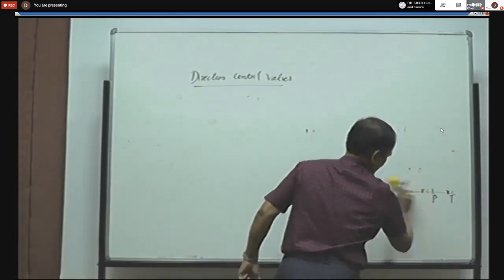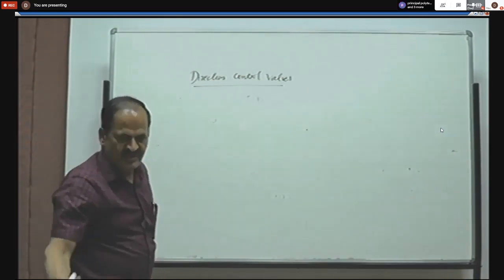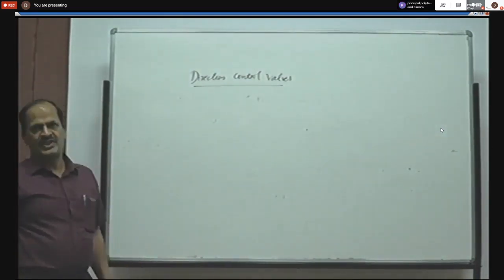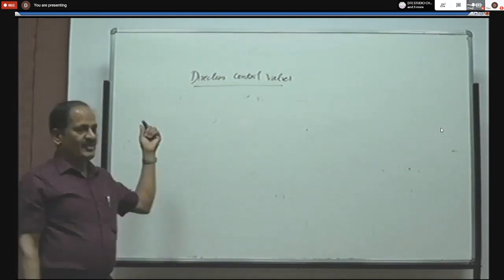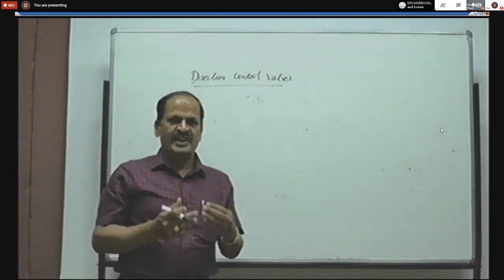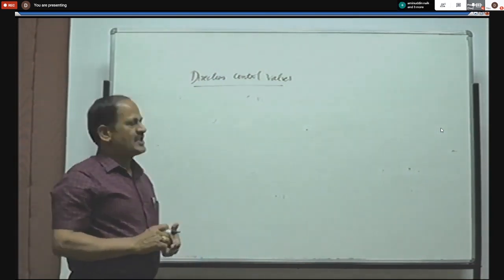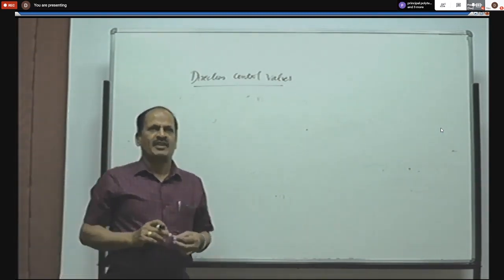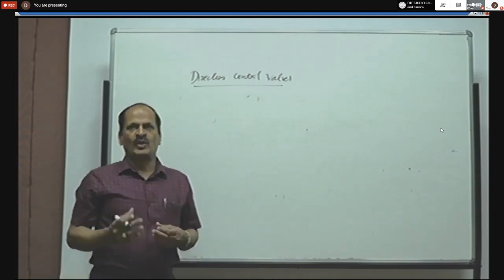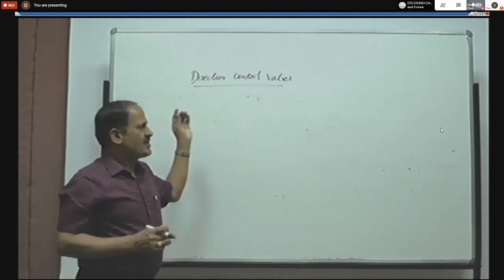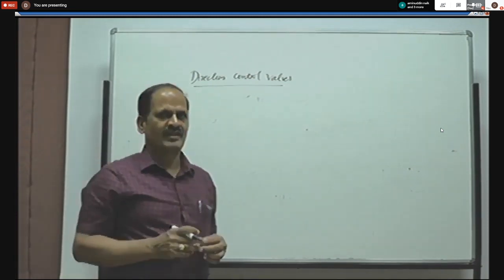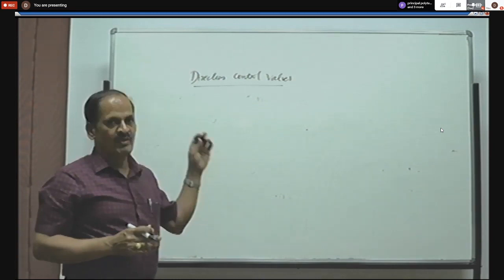There are three types of control valves used in hydraulic systems: pressure control valves, direction control valves, and flow control valves. In the case of pressure control valves, the pressure of fluid entering the actuator can be regulated and controlled — this is needed whenever the load is varying and pressure must be varied accordingly. In the case of direction control valves, the direction of flow of fluid entering the actuator can be changed or reversed by using direction control valves.